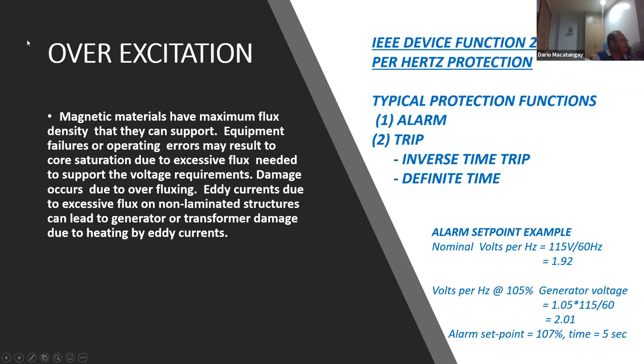Magnetic materials have a maximum flux density that they can support. Flux density is flux divided by the area. Of course, the more flux that needs to pass through a certain area, the more you have those hysteresis and eddy currents. Equipment failures or operating errors may result in core saturation due to excessive flux, meaning high voltage. Damage, of course, is due to overfluxing. Eddy currents due to excessive flux in non-laminated structures can lead to generator or transformer damage due to heating by eddy currents.